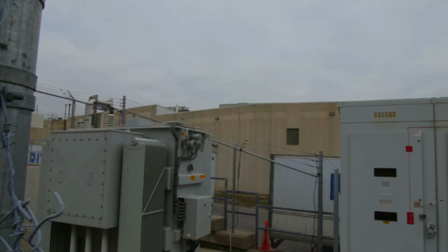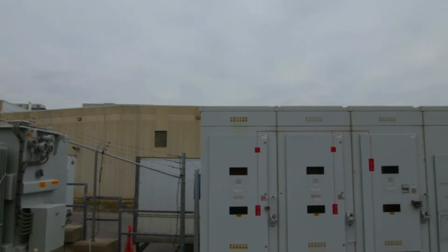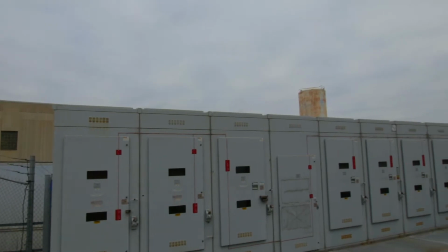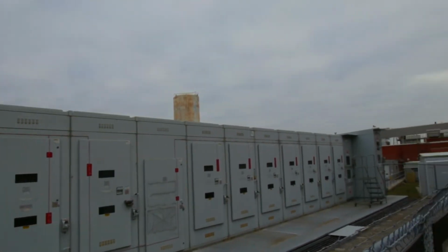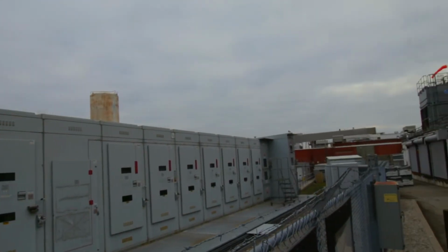And then once we leave that generator breaker, we have to step up the power for distribution throughout the Campbell's site. And so we have a 5 MVA transformer that steps the power from 13.8 kV to 27.6 kV. That's an oil-filled transformer. It's rated for outdoor installation. It can be equipped with fans if the system needs to be upgraded in the future.